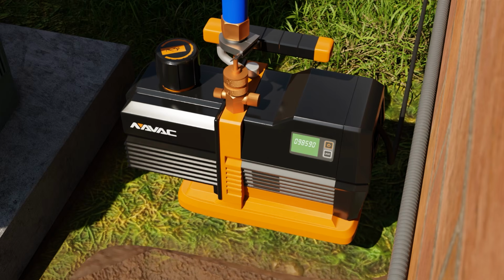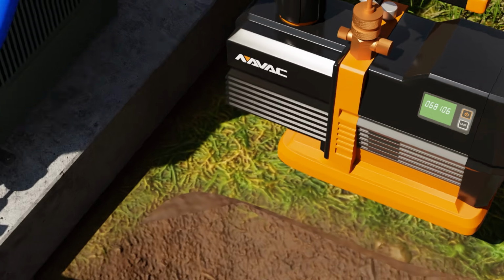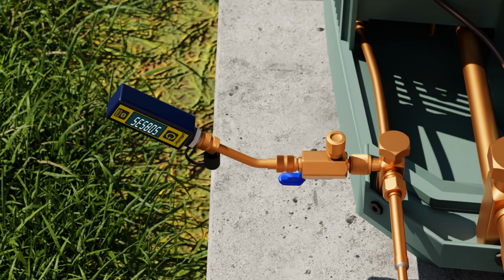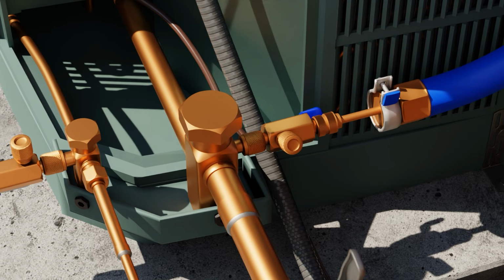and we try to get it below 300 microns. You're going to notice that this is significantly faster than when you're pulling on the entire system, like your condenser coil or your compressor after repair. This is because the only thing you're pulling a vacuum on right now are your copper lines and your evaporator coil. And since generally they're brand new, or they've been recently cleaned, it's not going to take a lot to get to a deep vacuum.